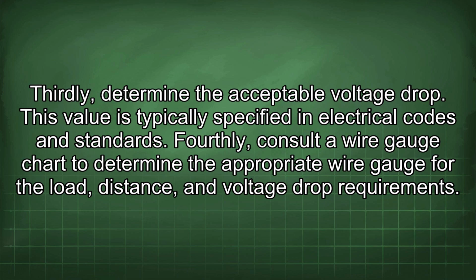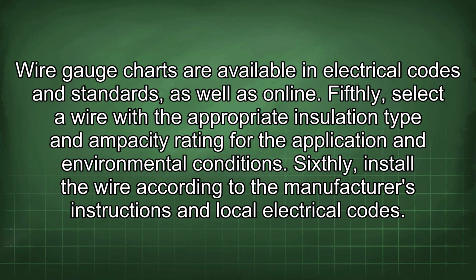Fourthly, consult a wire gauge chart to determine the appropriate wire gauge for the load, distance, and voltage drop requirements. Wire gauge charts are available in electrical codes and standards, as well as online. Fifthly, select a wire with the appropriate insulation type and the ampacity rating for the application and environmental conditions. Sixthly, install the wire according to the manufacturer's instructions and local electrical codes.